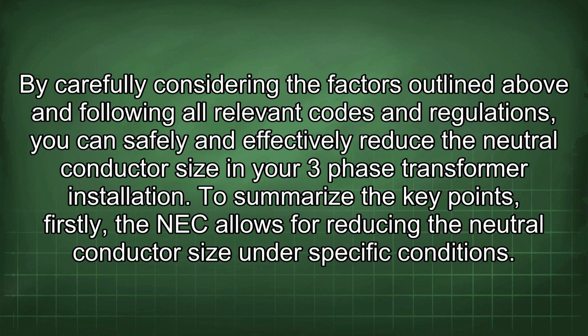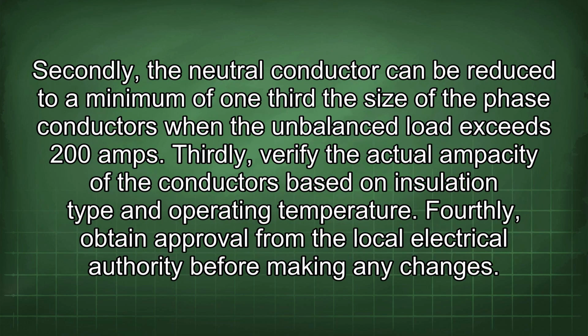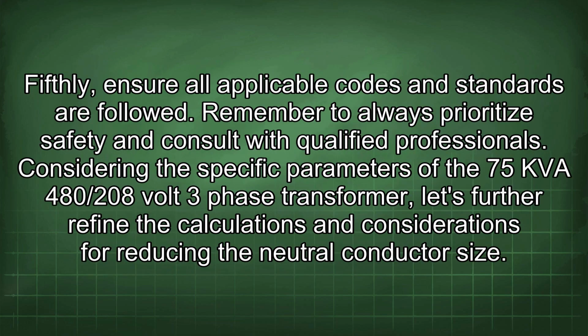To summarize the key points, firstly, the NEC allows for reducing the neutral conductor size under specific conditions. Secondly, the neutral conductor can be reduced to a minimum of 1/3 the size of the phase conductors when the unbalanced load exceeds 200 amps. Thirdly, verify the actual ampacity of the conductors based on insulation type and operating temperature. Fourthly, obtain approval from the local electrical authority before making any changes. Fifthly, ensure all applicable codes and standards are followed. Remember to always prioritize safety and consult with qualified professionals.